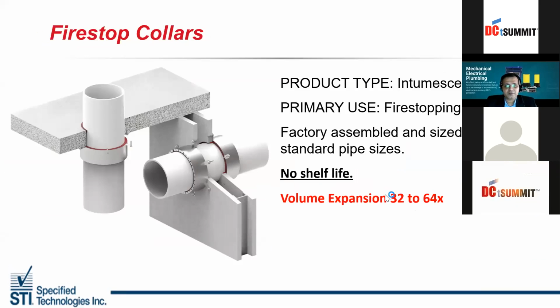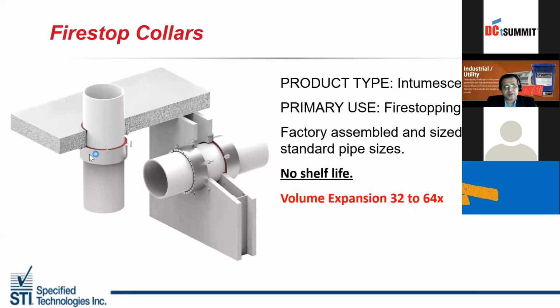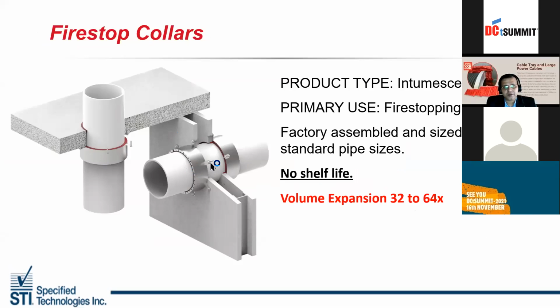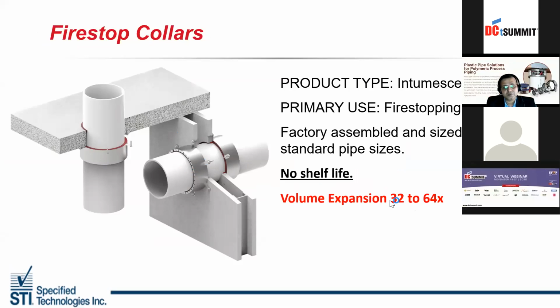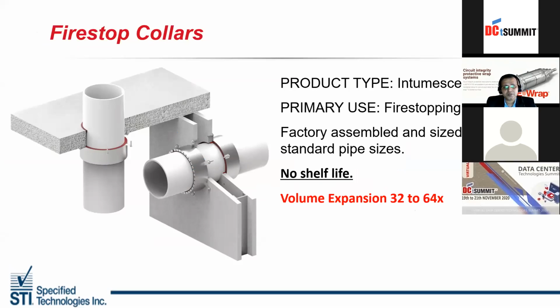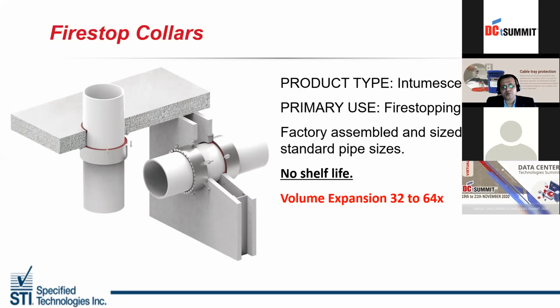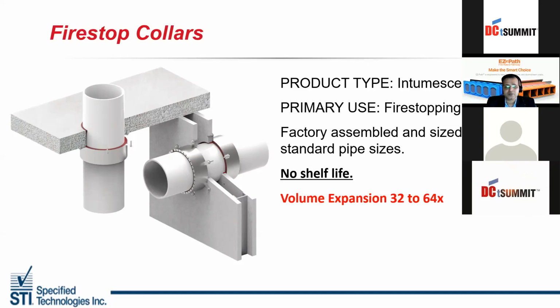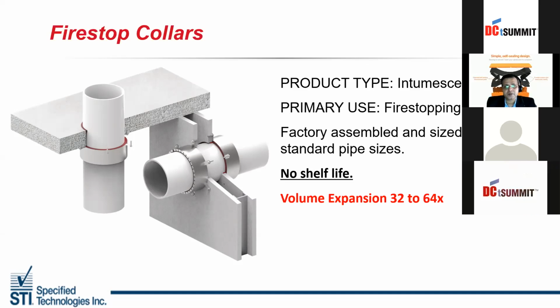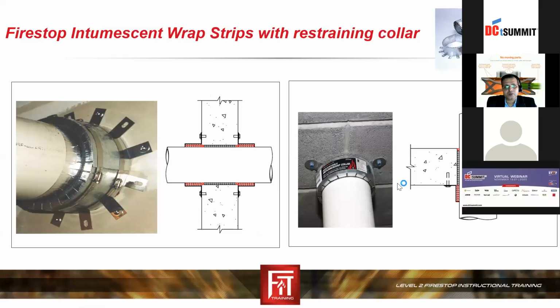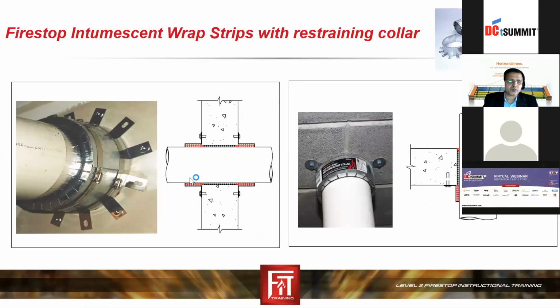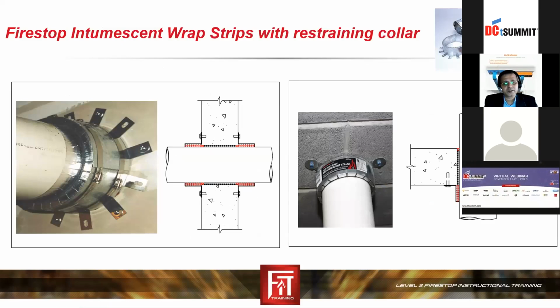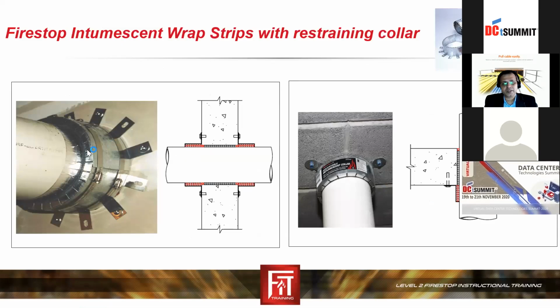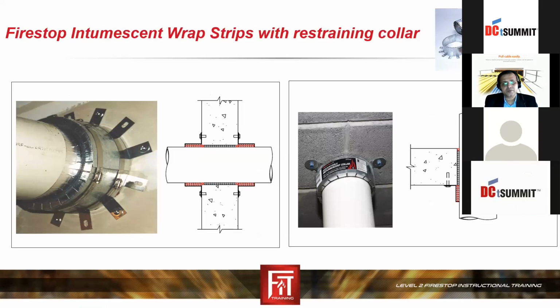Collars, as I explained earlier, I'm just trying to show why they are used in floor and wall scenarios. We have got multiple strips, wrap strips and collars, which will expand from 32 times to 64 times. Again, this product also doesn't have a shelf life. It can be used as per the site requirement. These collars are normally used from 4-inch, 6, 8, 12. Depending upon the size, collars are always from 4-inch onwards.